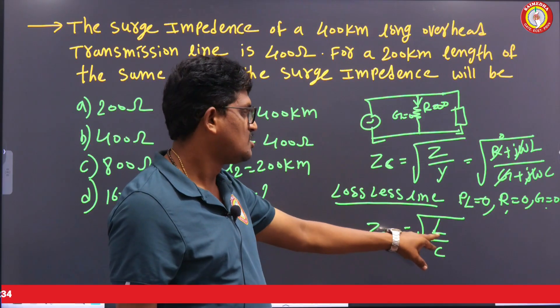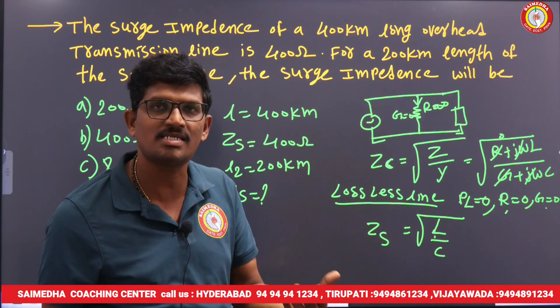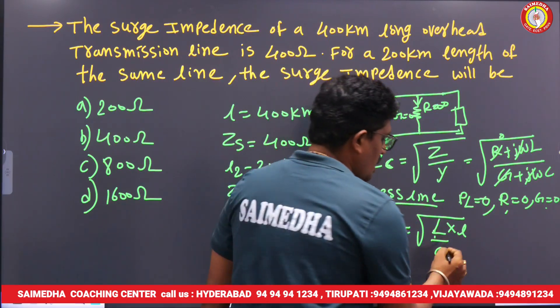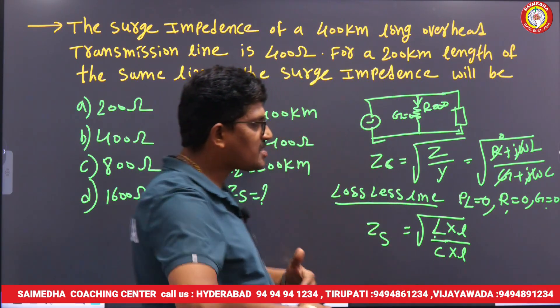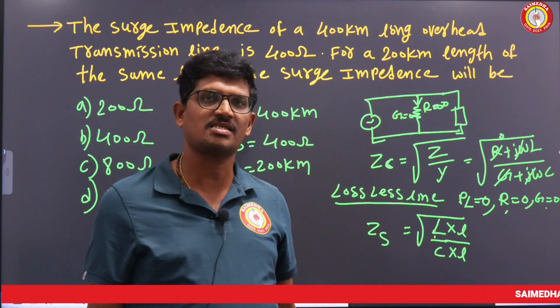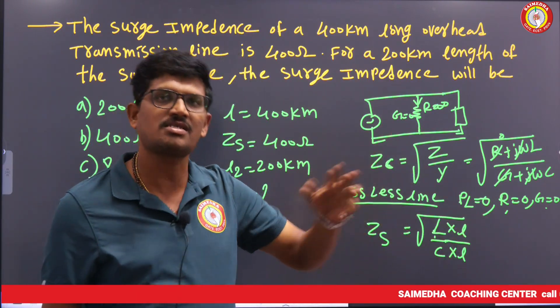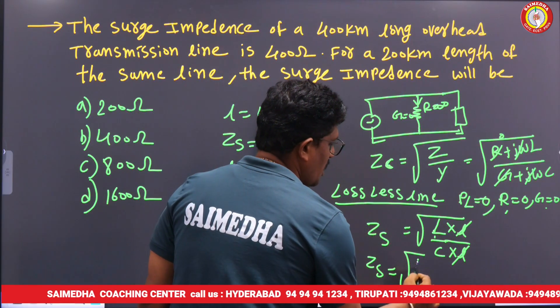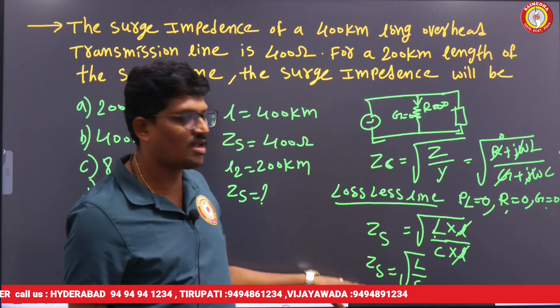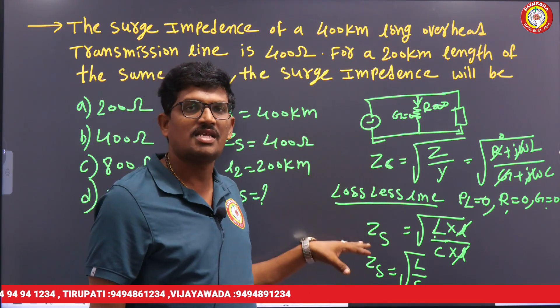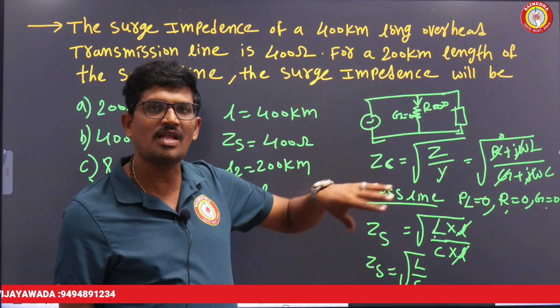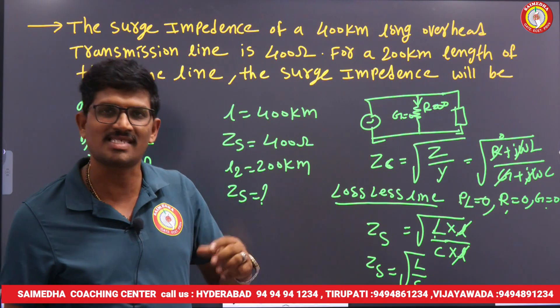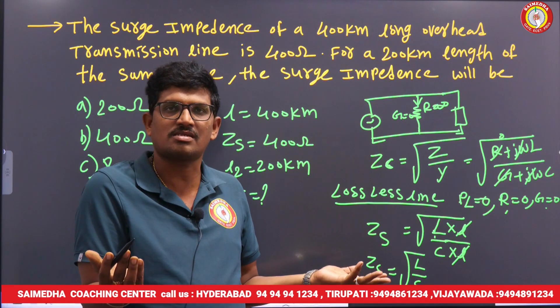The surge impedance formula is √(L/C), where L is inductance and C is capacitance. Inductance depends on length, and capacitance also depends on length. If line length increases, both L and C increase proportionally, so L/C remains constant. Therefore, surge impedance is independent of the length of the transmission line — there is no length term in this formula.